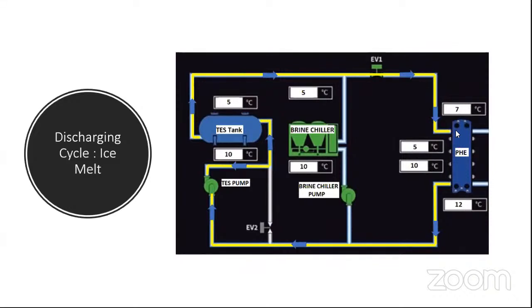So here you see the counterflow happening. From here, the brine is flowing, and from here, from bottom to top, the chill water is flowing. So 12 degrees centigrade chill water is entering, and 7 degrees centigrade chill water is coming out. That's how the cooling is happening on the load side. So here it is the load side. So that's our ice melting cycle. That is the discharging cycle. Now we'll see how ice is formed.